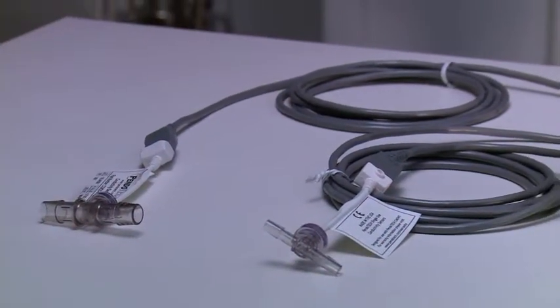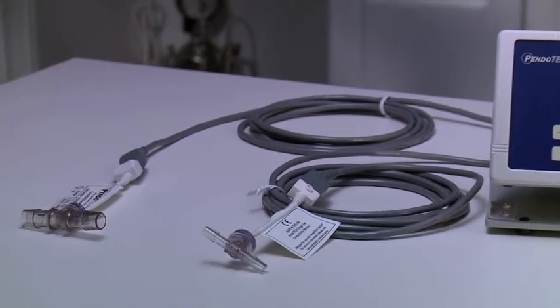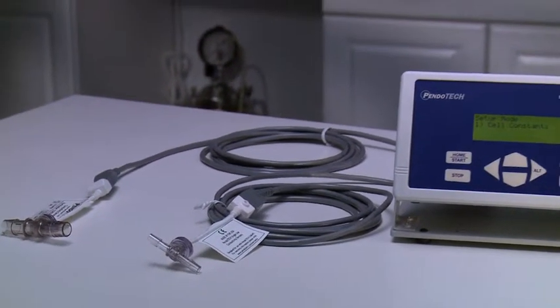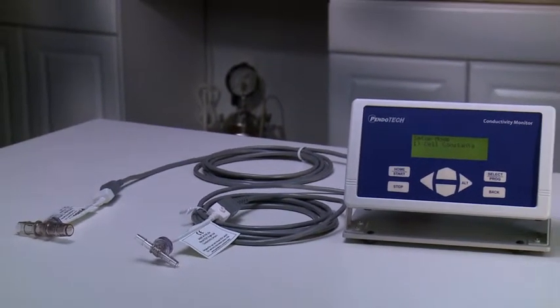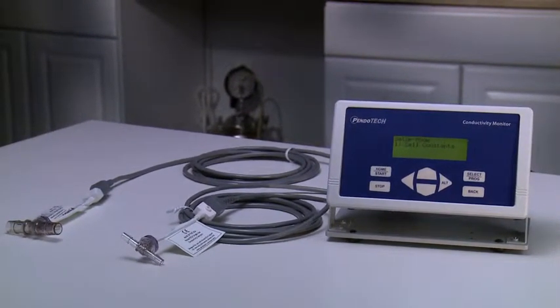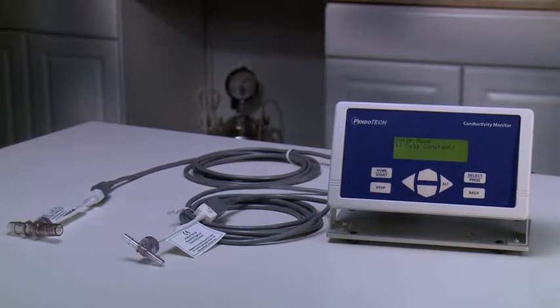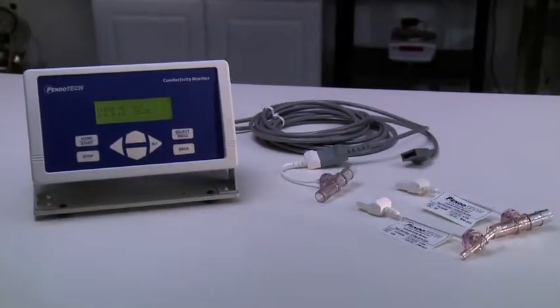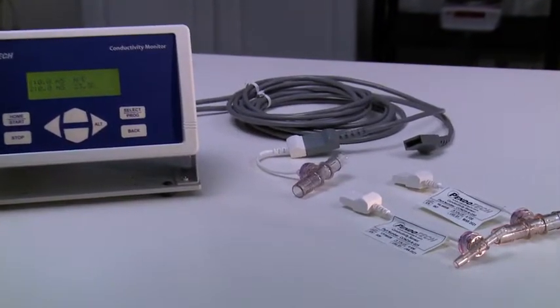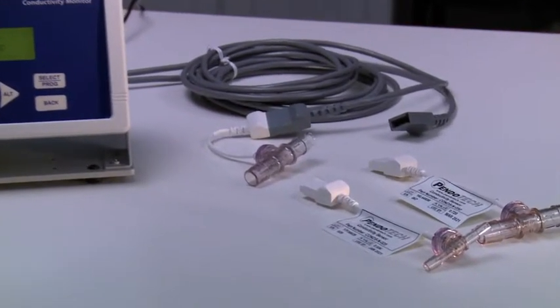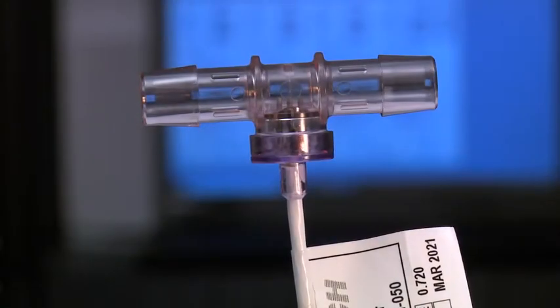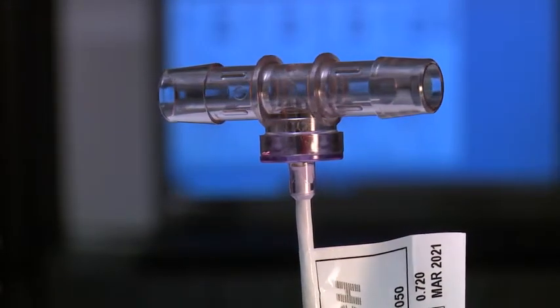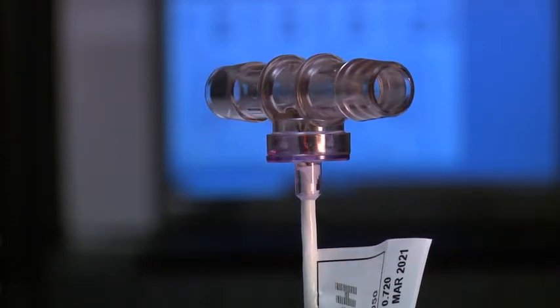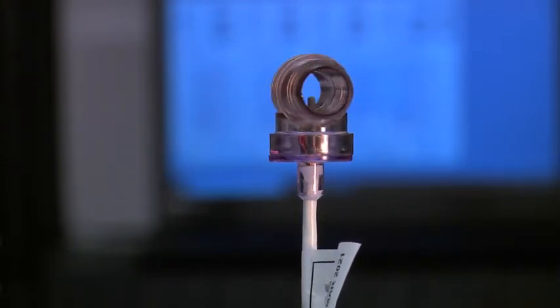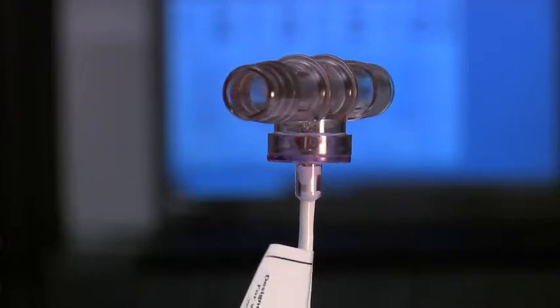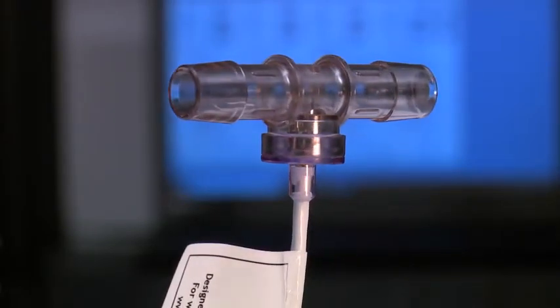The PendoTECH conductivity sensor, in combination with the CMONT monitor transmitter, enables measurement of liquid within the tube in the range from 0 to 100 millisiemens and temperature measurement and normalization to 25 degrees Celsius. Their unique properties and features make them amenable for uses in many applications in the biopharmaceutical industry. These single-use sensors have a revolutionary design which allows the parts of the product that come in contact with fluid to be disposable. This includes the conductivity electrodes and the temperature measurement element that is embedded in the tip of one of the electrodes.